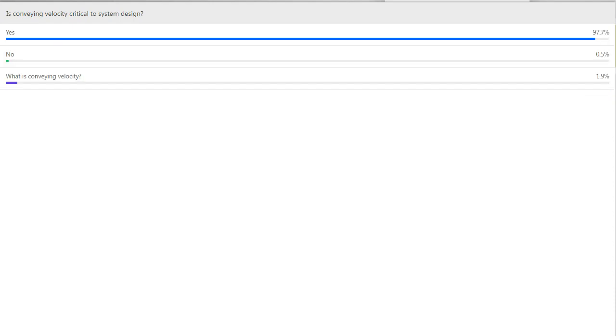So we have a good majority, 98% at yes. And for those of you that didn't understand that, not a problem, but the conveying velocity is how fast the airstream is moving. And in all industrial ventilation systems, the material is riding in the air. So we are only considering the air. The air is what's important, and you adjust the velocity dependent upon the heaviness of the particulate you're conveying.